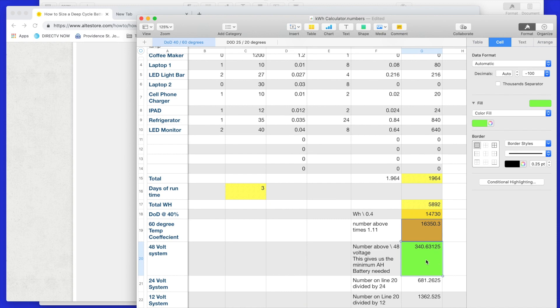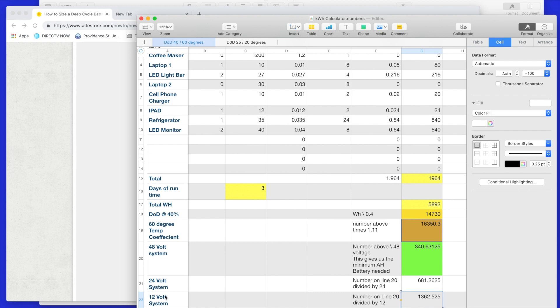So this gives you an idea. Now, just on all this, this just tells you the minimum amount, when you're looking at batteries, what you would need. If you want a 12-volt system, you better start shopping for some batteries out there that have 1,362 amp hours. And you're going to need 2 of them, right? 24, you're going to need 681, and you're going to need 4 of them. So this kind of lays the structure of your planning and capacity.